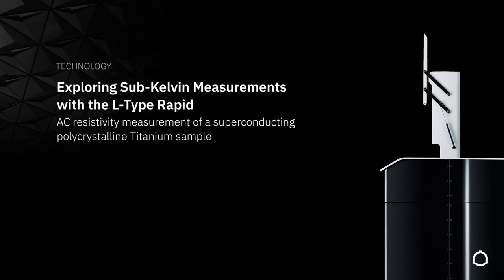Now, in the last part of this webinar, I would like to demonstrate how to use the L-type rapid and our instrument control and measurement software for a simple low temperature experiment. I will demonstrate how to carry out an AC resistivity measurement on a titanium sample where we track the superconducting transition at around 500 mK and suppress the transition by the application of an external magnetic field.